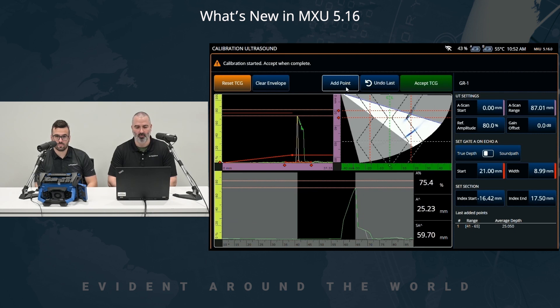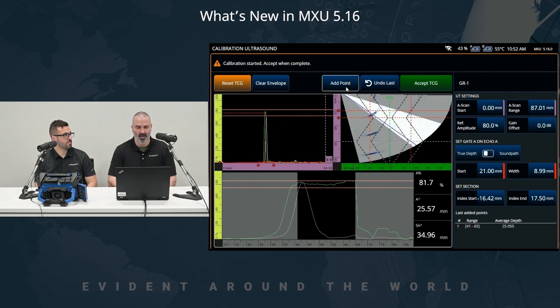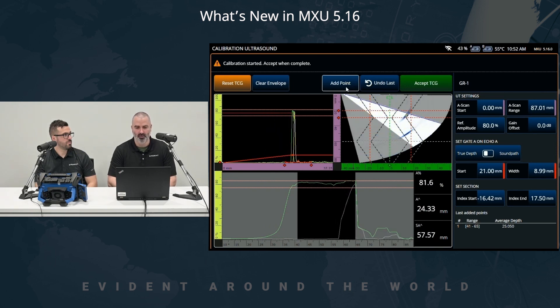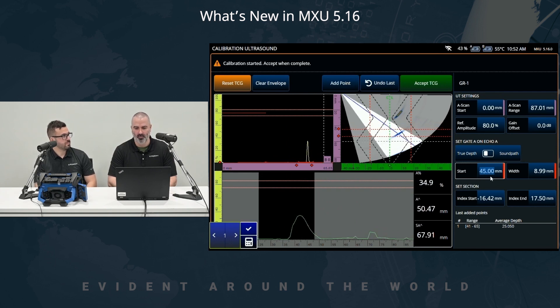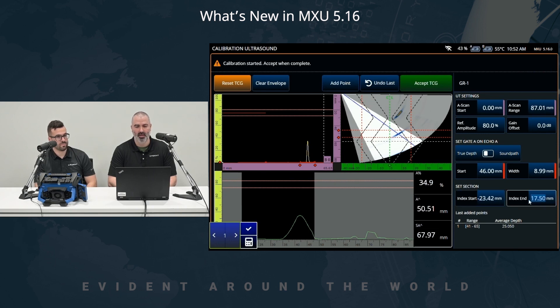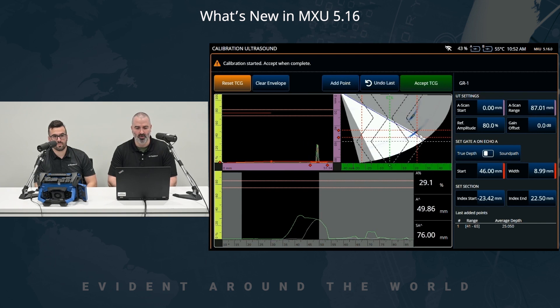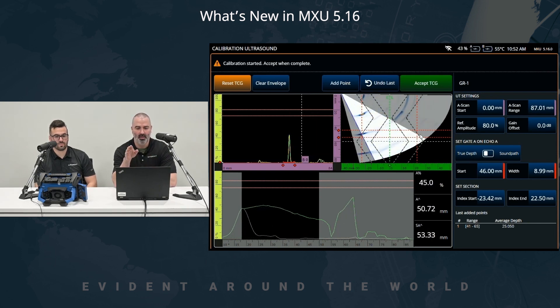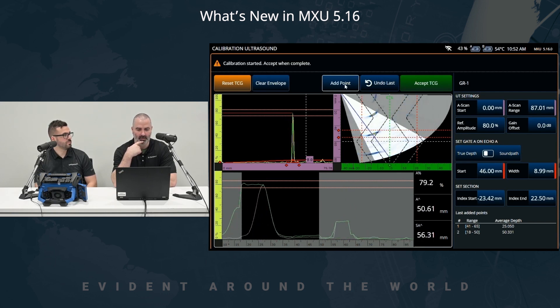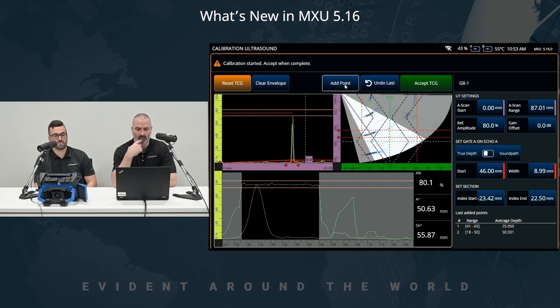During calibration, if I go back on the calibration — accounting for user manipulation errors and coupling differences — that doesn't look too bad. We're right on target for the half-thickness side drill hole. We can change the gate depth and move to the second side drill hole at two-thirds thickness, adjusting our index limiters to encompass the weld as well as the HAZ. We can see on the sectorial scan that we cover almost all the shallow angles and we don't calibrate the steep angles. We add the point and reviewing the calibration, we are at our reference level within the tolerance lines — those are our two side drill holes.